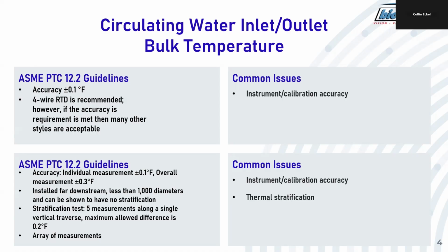I will be referring to ASME PTC 12.2 for each of the essential parameters. The information outlined in the test codes is very valuable. It is the goal or target for each of these parameters. We may not be able to achieve the PTC 12.2 recommendations fully, but the goal is to get as close as possible. We're going to start off looking at the inlet temperature.